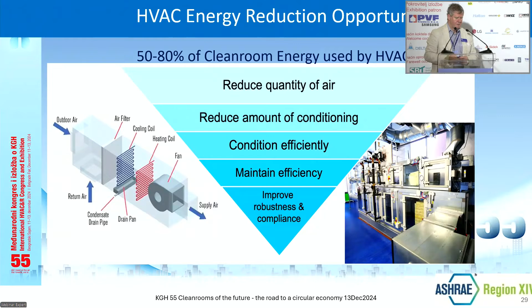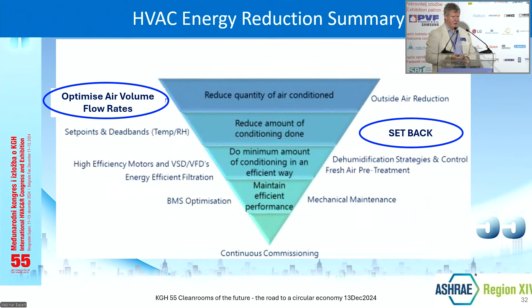Okay. But one of the things I am going to jump to, if I can, is that as a summary of reduction, the first two things we need to do in clean rooms today is to optimize the air volume flow rates. Not air change rates, air volume flow rates, to be effective. And the second thing is when you're not using your clean room, to put it into setback mode. Because if you're not using the clean room, you're not manufacturing, you're not providing a service, then you don't have any hazard or contamination generation within the space to remove.